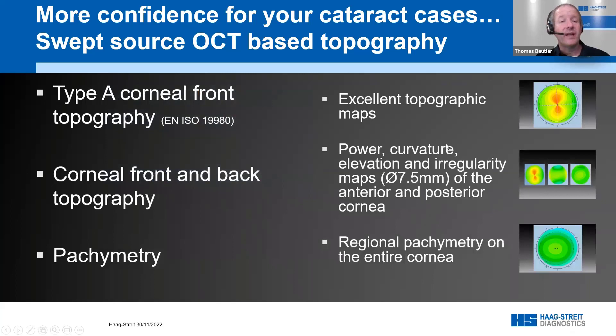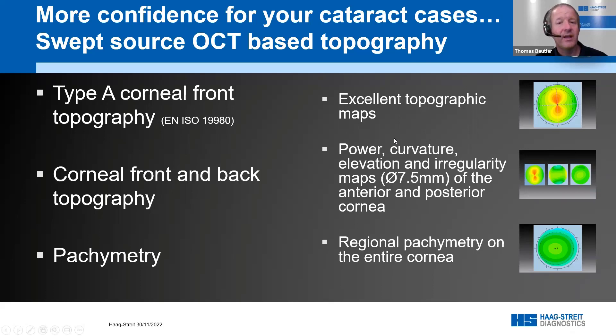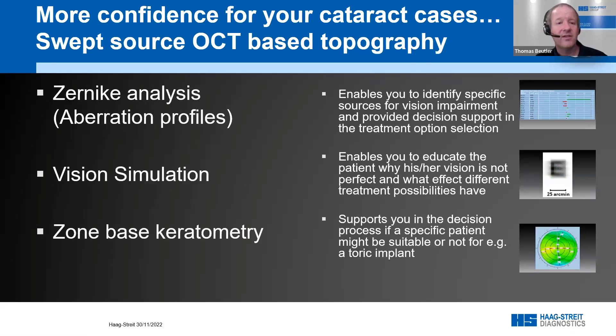An additional point: the topography provided by the iStar complies with Type A standard topography. It is a real topographer with corneal front and back topography in the cataract suite, covering 7.5 mm — suitable for standard applications. It also offers pachymetry, so you have corneal front, corneal back topography, and pachymetry all in one single measurement process. You get Zernike analysis with the aberration profile, vision simulation, and zone-based keratometry to judge whether a patient is a suitable toric candidate.